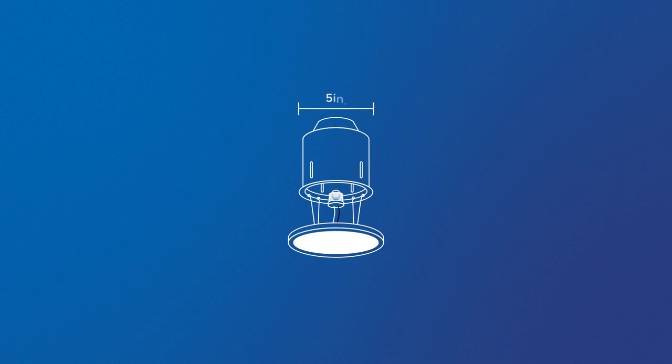recessed can, which requires a 5-inch can with a minimum depth of 5.5 inches, or a 6-inch can with a minimum depth of 5.8 inches.